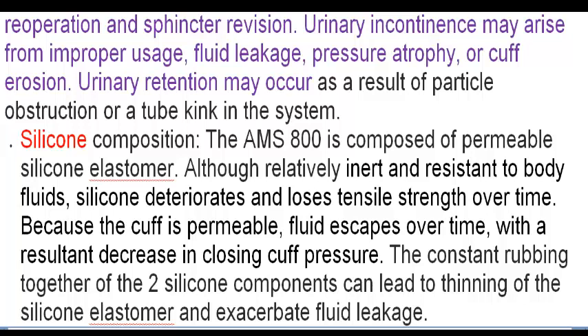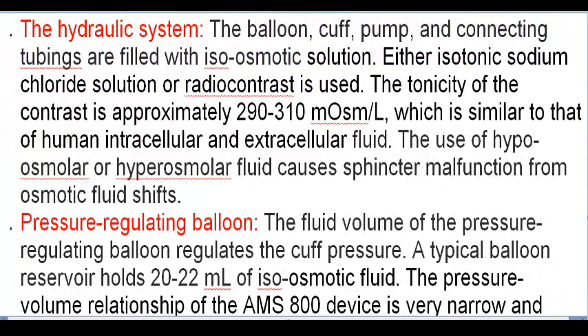Silicone composition. The AMS 800 is composed of permeable silicone elastomer. Although relatively inert and resistant to body fluids, silicone deteriorates and loses tensile strength over time. Because the cuff is permeable, fluid escapes over time, with the resultant decrease in closing cuff pressure. The constant rubbing together of the two silicone components can lead to thinning of the silicone elastomer and exacerbate fluid leakage.